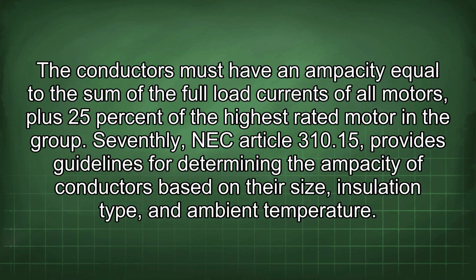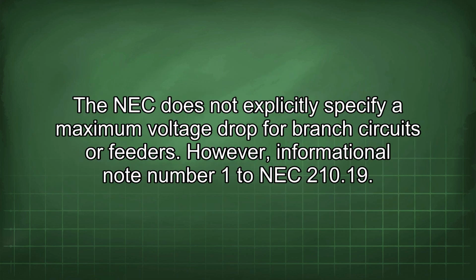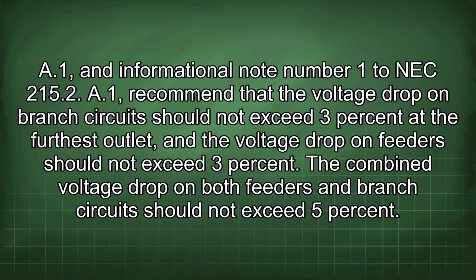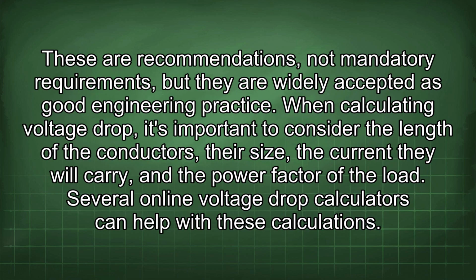Seventhly, NEC Article 310.15 provides guidelines for determining the ampacity of conductors based on their size, insulation type, and ambient temperature. The NEC does not explicitly specify a maximum voltage drop for branch circuits or feeders. However, Informational Note Number 1 to NEC 210.19(A)(1) and Informational Note Number 1 to NEC 215.2(A)(1) recommend that the voltage drop on branch circuits should not exceed 3% at the furthest outlet, and the voltage drop on feeders should not exceed 3%. The combined voltage drop on both feeders and branch circuits should not exceed 5%. These are recommendations, not mandatory requirements, but they are widely accepted as good engineering practice.